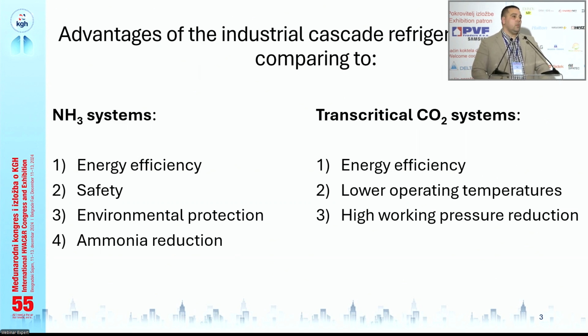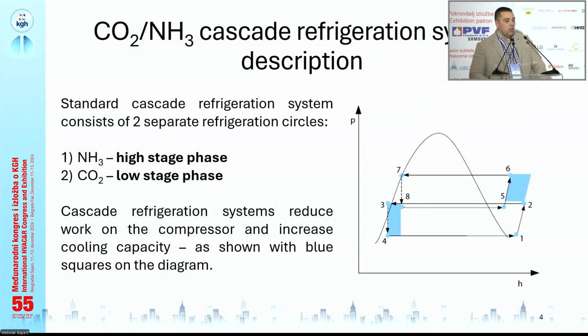Compared to transcritical CO2 systems, again, we can find some energy efficiency, especially when the outside ambient temperature goes high, because transcritical CO2 systems lose their efficiency particularly when we have high ambient temperature. And also with this cascade system, we have lower operating temperatures and pressures, which at some point can be beneficial due to lower investment costs for some parts and materials that require lower pressure.